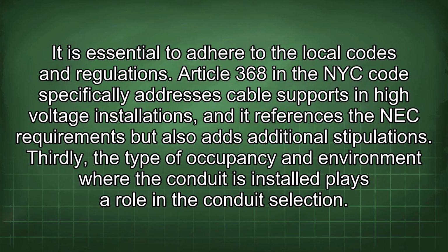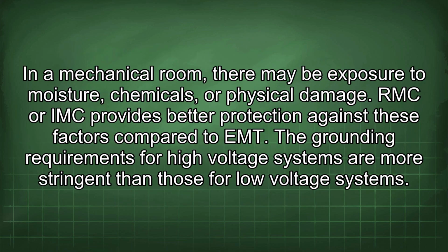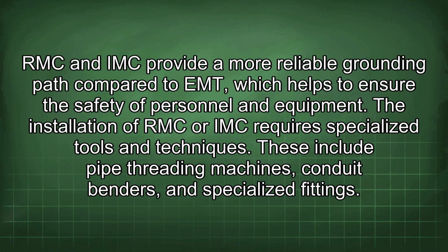Article 368 in the NYC Code specifically addresses cable supports in high-voltage installations, and it references the NEC requirements but also adds additional stipulations. Thirdly, the type of occupancy and environment where the conduit is installed plays a role in the conduit selection. In a mechanical room, there may be exposure to moisture, chemicals, or physical damage. RMC or IMC provides better protection against these factors compared to EMT. The grounding requirements for high-voltage systems are more stringent than those for low-voltage systems.